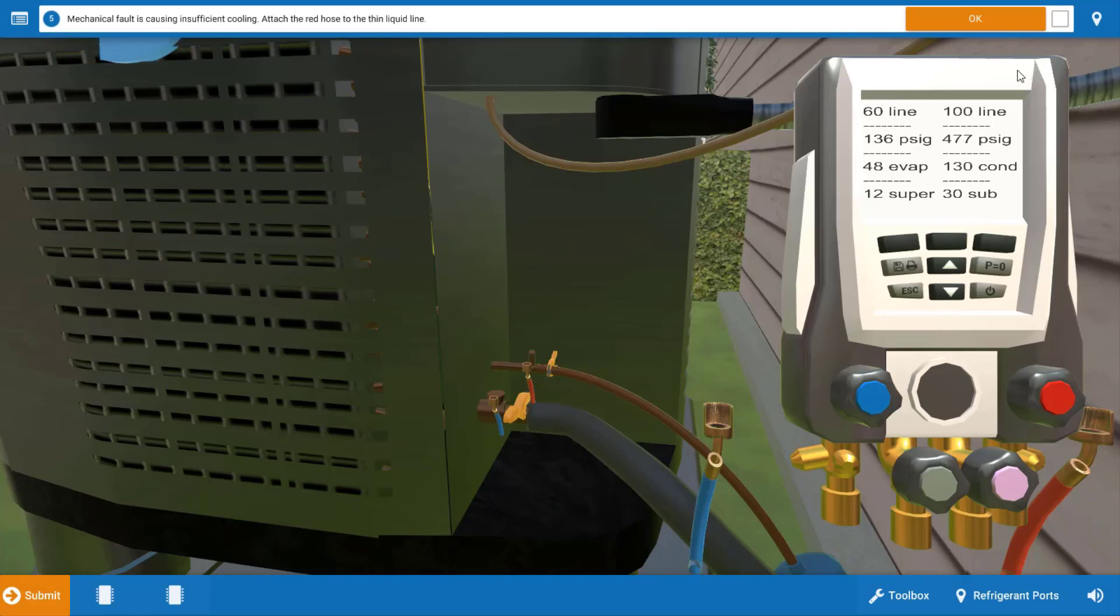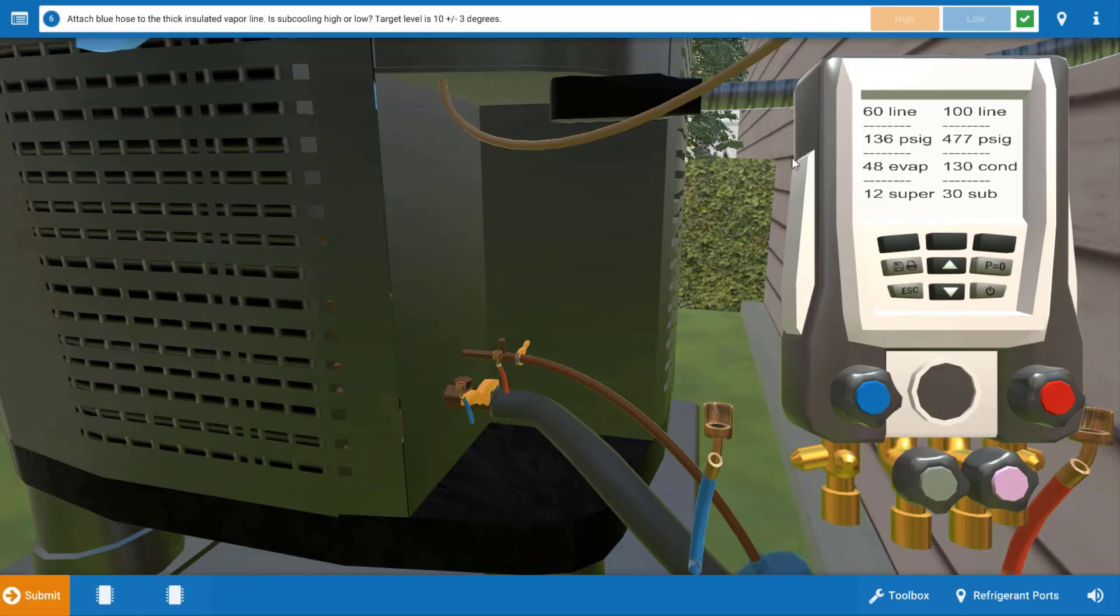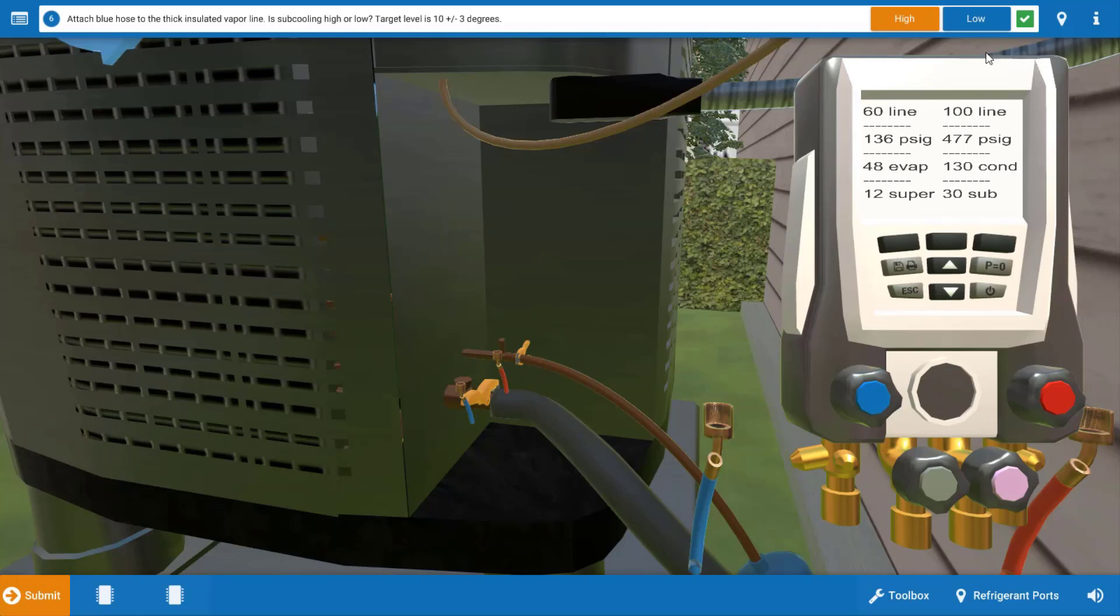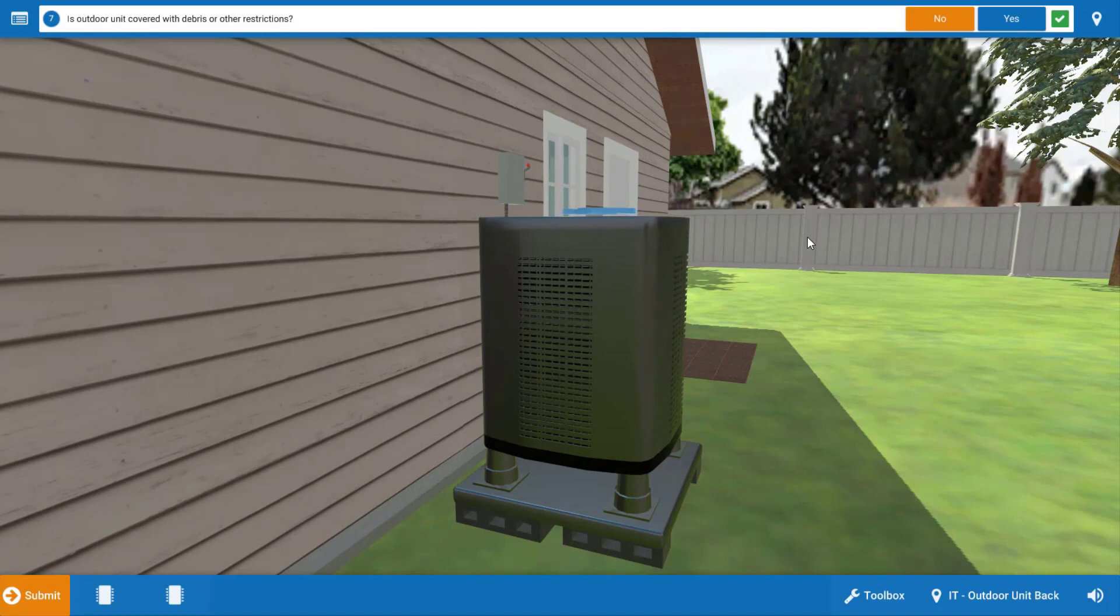We pretty much know that the unit is overcharged at this point. We're going to click OK in the procedure guide and we've determined that we're definitely not within the target plus or minus three of the 13 degrees and our subcooling is high here, not low. It's 30 instead of 13. Again, that subcooling margin that you measure only needs to be within plus or minus three of the target of 13.